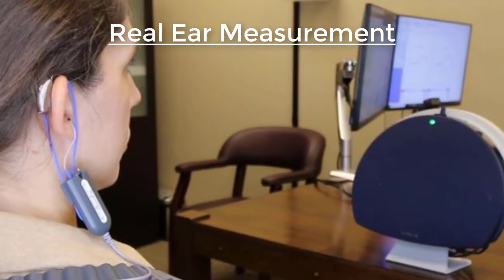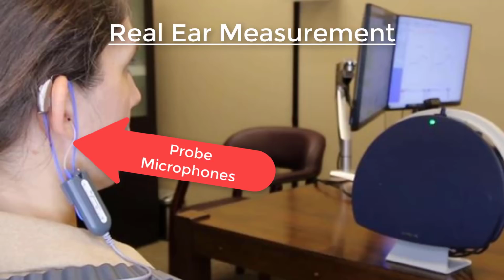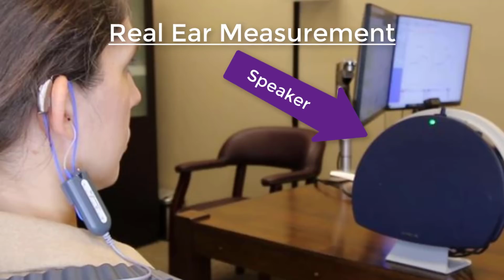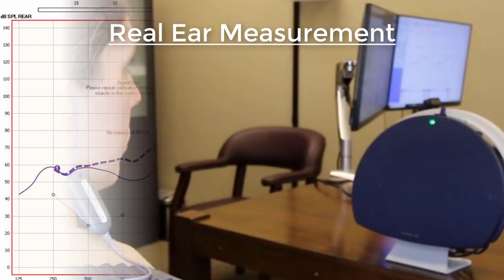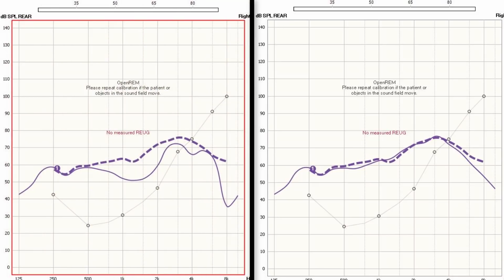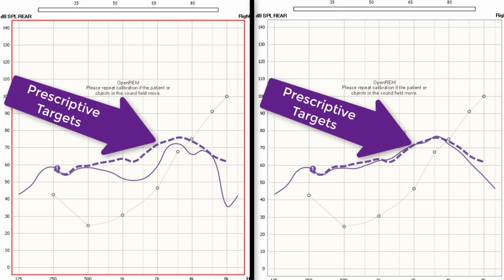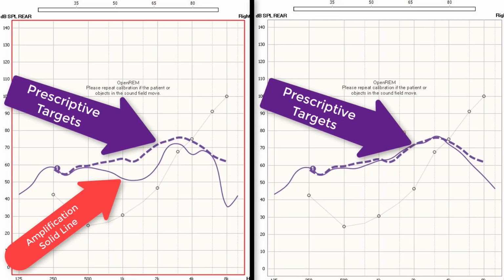How this process works is your hearing care provider will place probe microphone tubes inside of your ear canals along with the hearing aids that they are programming. These microphone tubes will record the level of amplification coming out of the hearing aids. By playing a known calibrated signal from a loudspeaker in front of you, we can measure to see if the amplification coming out of the hearing aids is meeting your prescriptive targets. When we look at these measurements on a screen, we see the prescriptive targets for sound indicated by the purple hash mark line. The solid purple line indicates the sound coming out of the hearing aid after it has been amplified. The goal is to have these lines overlap as closely as possible.